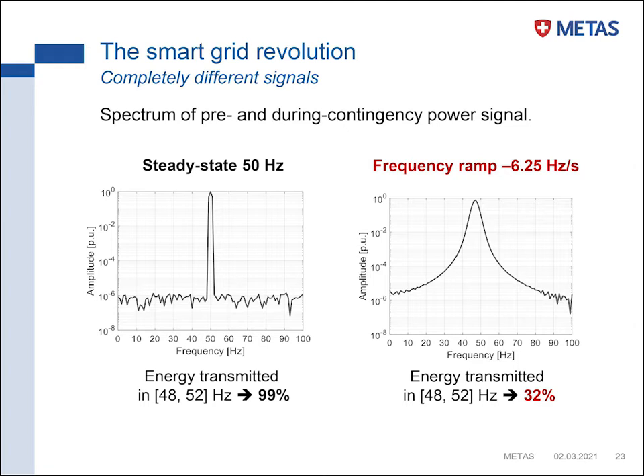But during a dramatic event like South Australia, we deal with a continuous spectrum where just a third of the energy is around 50 hertz. It's also mathematically challenging to define what frequency means when the spectrum has this particular shape, and this is very challenging because the metering system has to give us this information to take the most appropriate control actions.